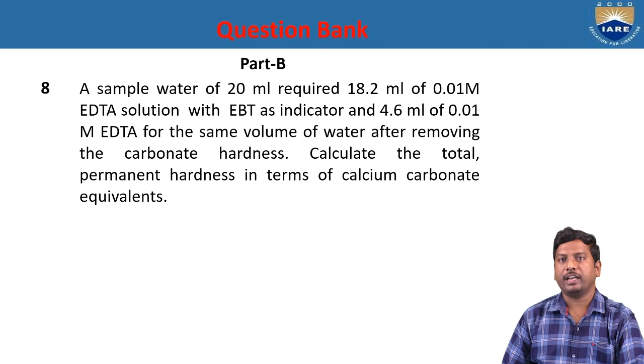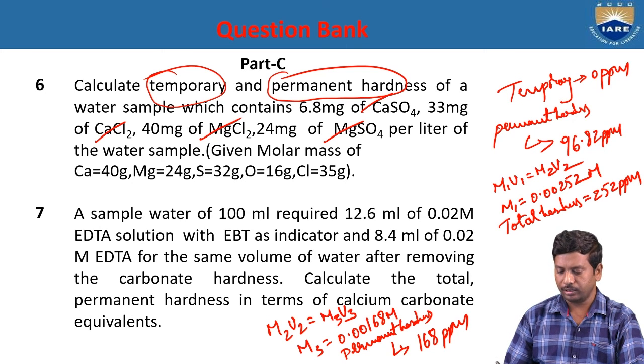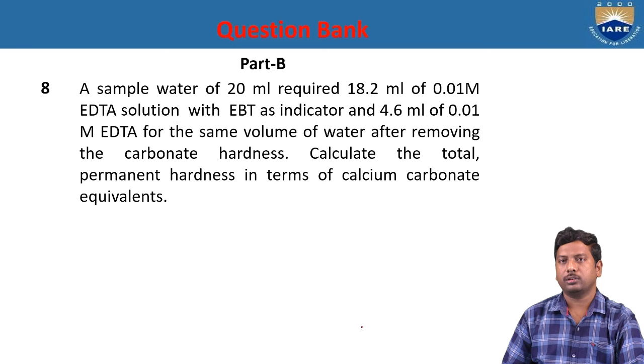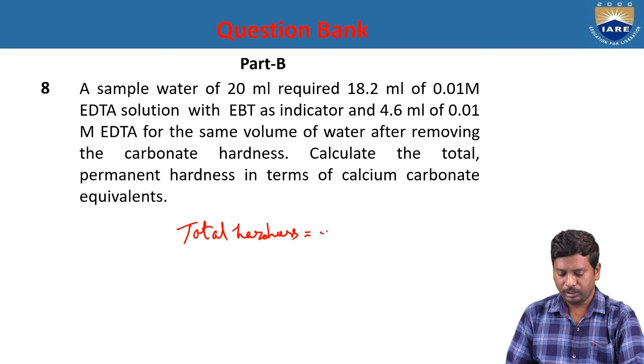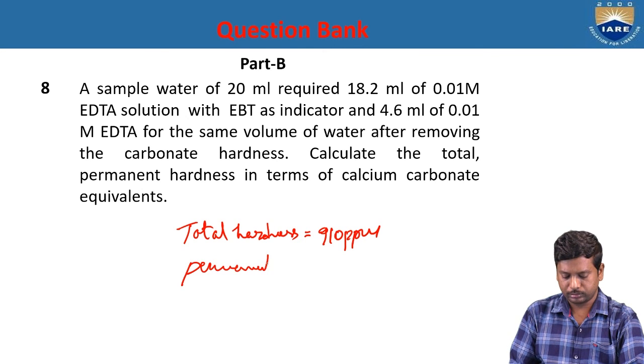Problem 8: A water sample of 20 ml required 18.2 ml of 0.01 molar EDTA solution with EBT as indicator, and 4.6 ml of 0.01 molar EDTA for the same volume after removing carbonate hardness. Calculate total and permanent hardness in terms of calcium carbonate equivalence. Total hardness = 910 ppm and permanent hardness = 230 ppm.